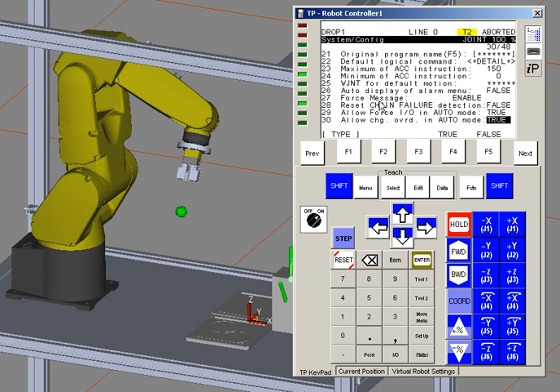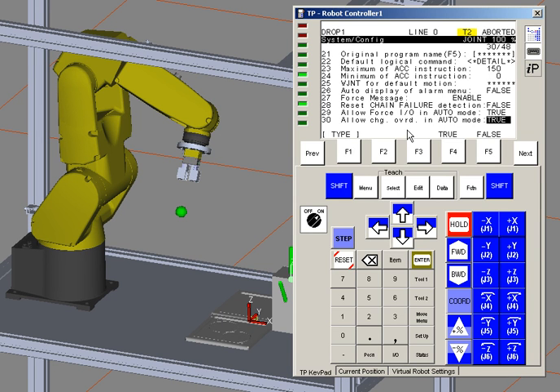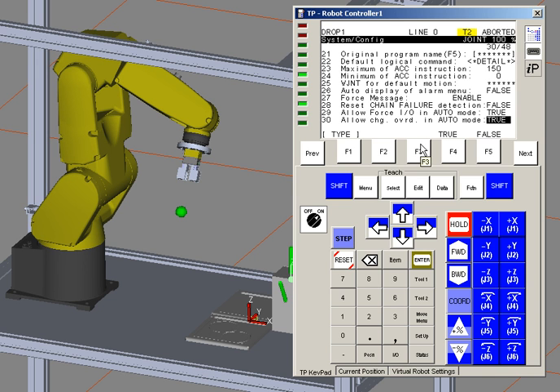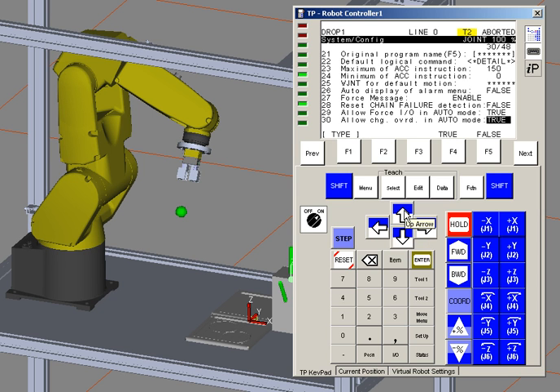These force messages, allowing force and allowing change override in auto mode, those are important items to consider when looking at production systems. Basically, in this statement, you would allow the operator to force inputs and outputs on your controller while in production in automatic mode. Typically, we want those turned to false so that it is not possible.